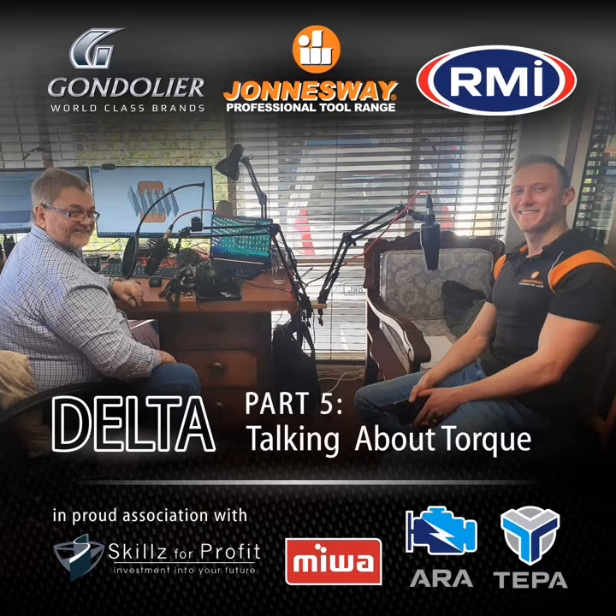So what you're advocating is that a torque wrench should be released to zero after every job, and then reset for the next job on a day, every time there's a need for the use of a torque wrench. Is that correct? That's 100%. So basically what happens is, like I said, you've got a pretty big spring inside your torque wrench. If that spring is under compression for, let's say, a week, and you then go back onto zero, that spring's tension isn't going to be as strong as it used to be. That's where the quality comes in. It's still not an ideal thing to do, but if you do it, the quality is going to help you a lot more, so that you don't have to recalibrate your torque wrench every week or month or whatever. Pretty much like leaving a 1-ton load on the back of a 1-ton bakkie for a couple of weeks. 100%. It's going to destroy the springs.